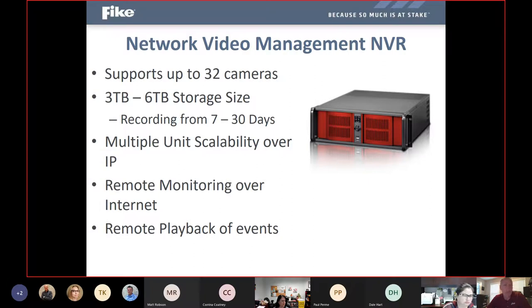We have some pretty complex and complicated networks in a lot of pretty high profile locations around the country, some of which have upwards of 100 to 200 cameras all in the same network. Since it is a camera-based system, we can easily achieve remote monitoring over the internet. So this either can or may not be attached to whatever internal network the customer or the end user has at their site, and to where they might have a screen or a workstation dedicated just to this system, or it can be on their common shared network where anybody at any time could go find a camera and pull the video feed from it to see what that camera is seeing and go into its history and see what detection events it might have had over the course of the last week or so to see what led up to potentially a fire occurring.